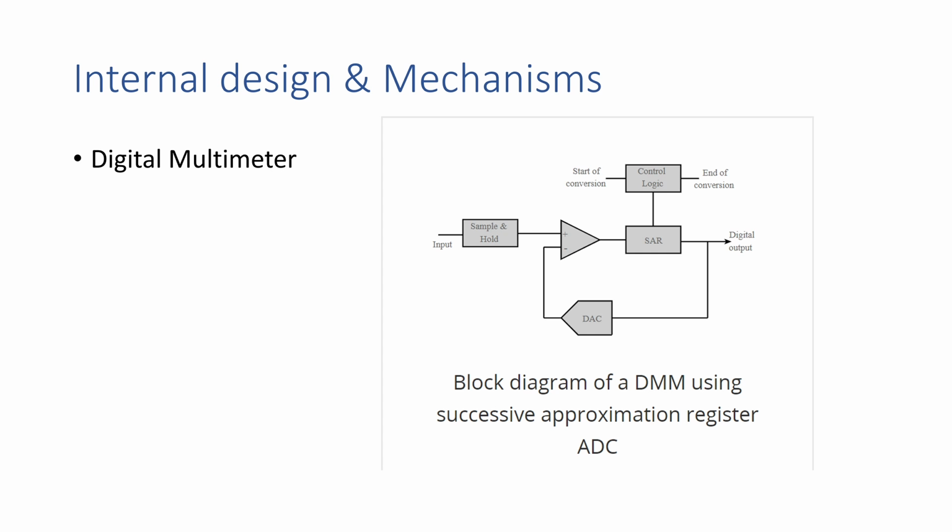This level of speed is more than adequate for most DMM applications, where high levels of speed are not normally required. Typically, for most bench or general test instrument, measurements only need to be taken at a maximum rate of a few a second, possibly 10 a second.